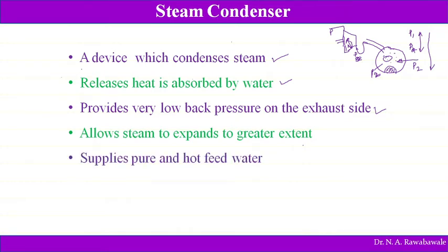Next one, it supplies pure and hot water. The condensate which is collected in the condenser is pure water, and that pure water is recirculated as feed water to the boiler. If we supply pure water to the boiler, it contains no salt particles or other sediments, and because of that the life of the boiler will increase, or the system life will increase, or there will be minimum corrosion. So the cost of pure water is very high.